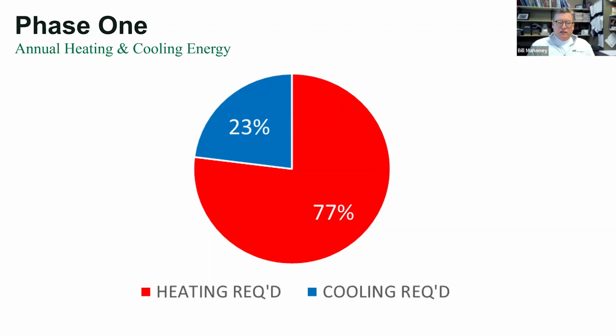So again, we've got this ground source heat exchanger, and like I said, in the summertime we're going to put heat into the ground, and in the wintertime, we're going to extract the same heat back out of the ground. Now, this is just looking at phase one, so it's just a quarter of the campus, and how much annual heating and cooling the buildings need. Forget about the system, but the buildings require a kind of 3-to-1 balance. So a quarter of the annual energy was used for cooling, 3/4 for heating for our mix of buildings with all those high residential buildings, heating only, right?